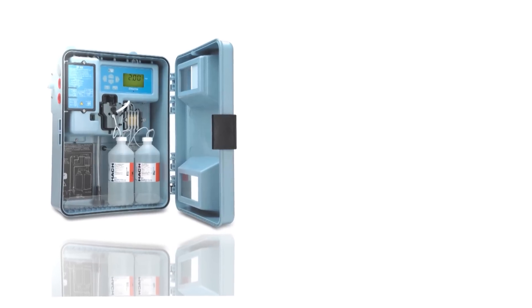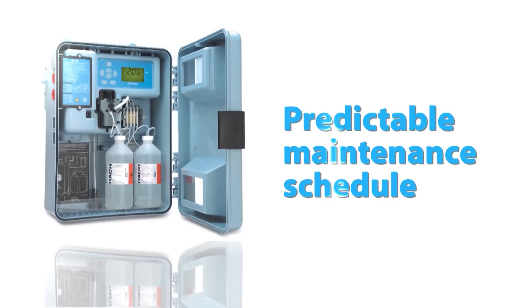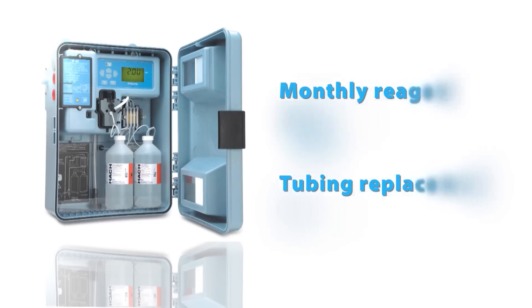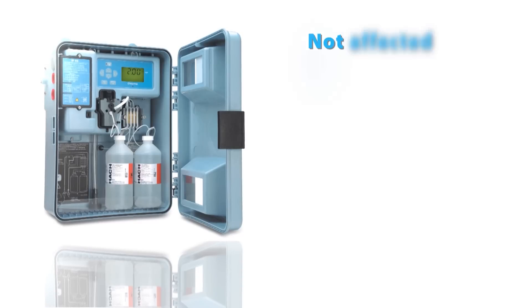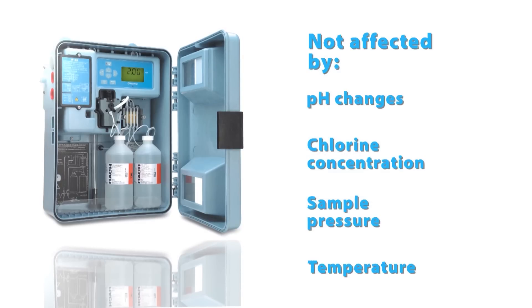Highlights of the Hach CL17 include reliability, ease of use, and a predictable maintenance schedule consisting of monthly reagent replacement and tube replacement twice a year. The CL17 does not require user calibration and is not affected by changes in pH, chlorine concentration, sample pressure, or temperature.